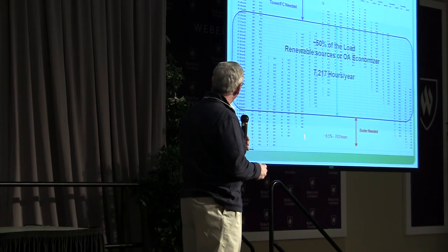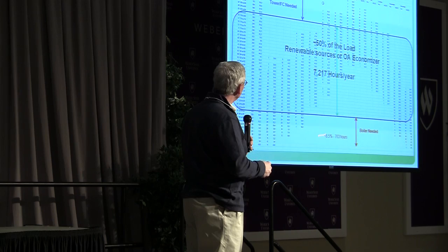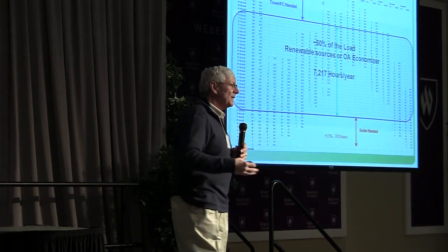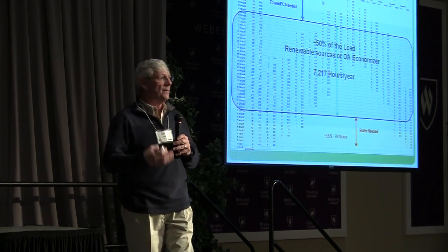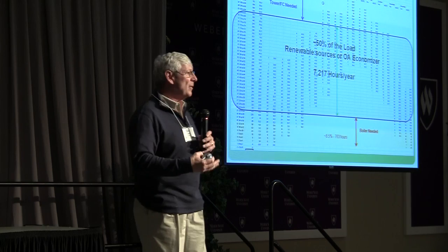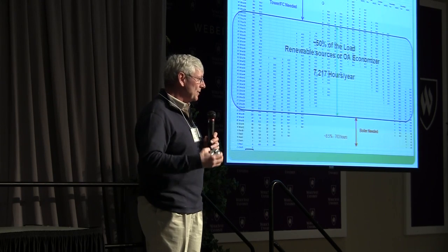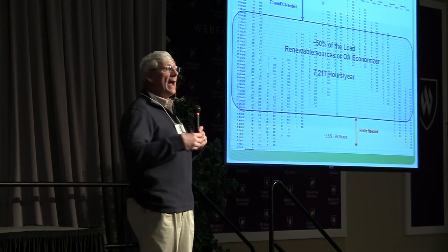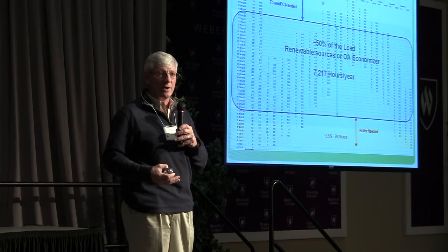And then we need a boiler at the end to handle it. We either bleed it in or start to supplement the system. The general idea is to keep the temperature entering the heat pump at an optimum level so we get the highest coefficient of performance and the highest energy efficiency ratios.